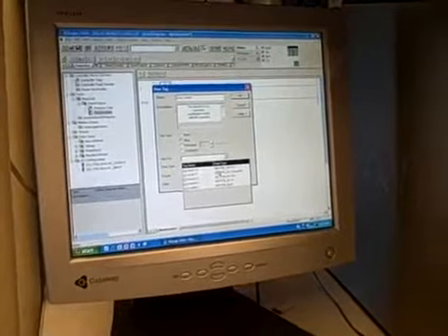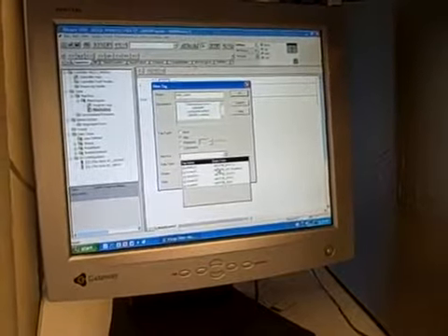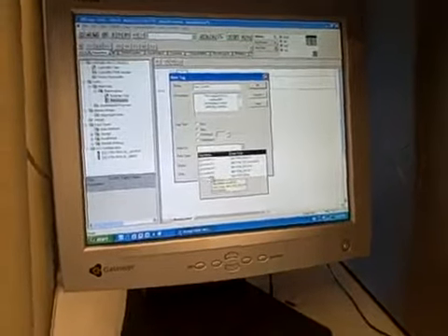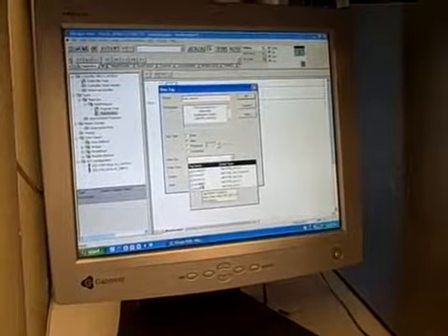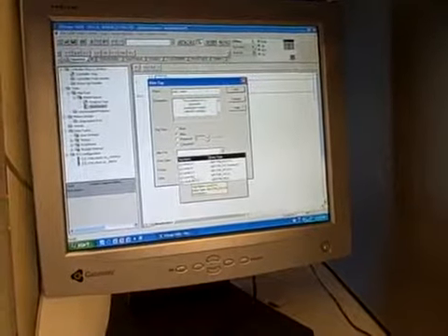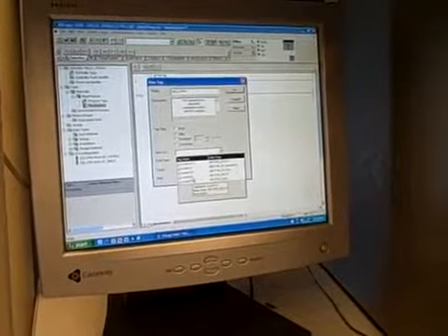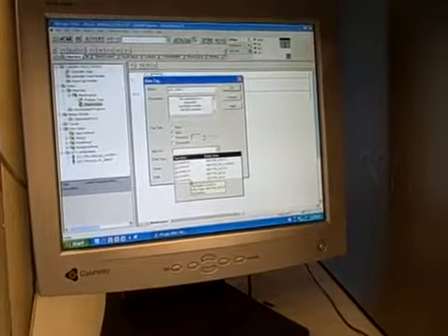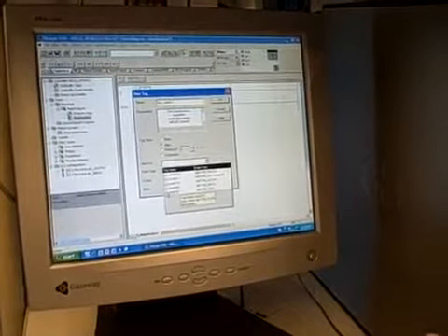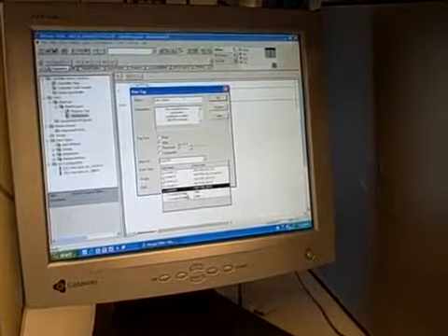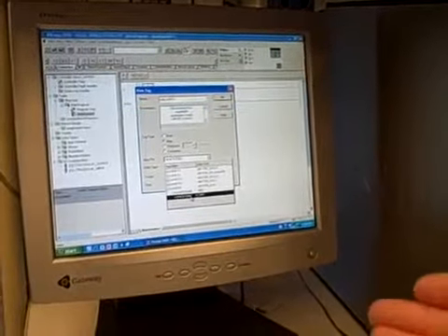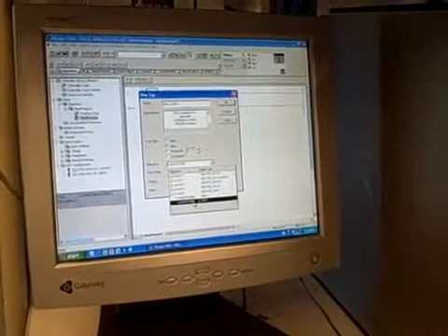So remember, this is for a start switch. This is an input, and our input card was on slot 9. When we go down here to our tag names, it shows the physical addresses here of the various cards. We know that slot 9 is our input card, our digital input. We have a couple of different sets of variables, one with a C, one with an I. The I refers to input, and the C refers to configuration. So here I want the I, I can expand that. And I've got fault information and also data right here. I want the data. This is going to be the actual bits turned on and off by switches connected to the inputs.